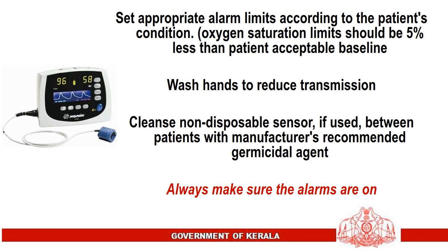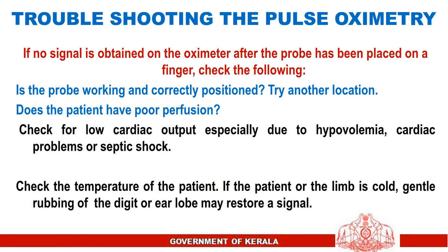Always make sure that the alarms are on. Troubleshooting: if no signal is obtained after the probe has been placed on a finger, check the following — is the probe working correctly? The patient may have poor perfusion; check for low cardiac output especially due to hypovolemia, cardiac problems, or septic shock. Check the temperature of the patient — if the patient or the limb is cold, gentle rubbing of the digit or ear lobe may restore a signal.